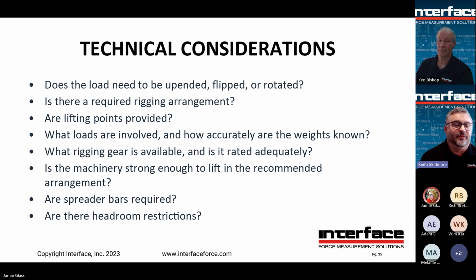We have something up in the air and people standing around, and now you're wondering how it's going to move safely. Is there special rigging arrangements required? The manufacturer may specify lift points and certain methods. Those need to be followed. So it's important to understand if something may have a required or a suggested arrangement for moving it, that needs to be noted. Again, are lifting points provided? If something is intended to be lifted, it should have lift points not only provided but visibly marked or in the documentation.